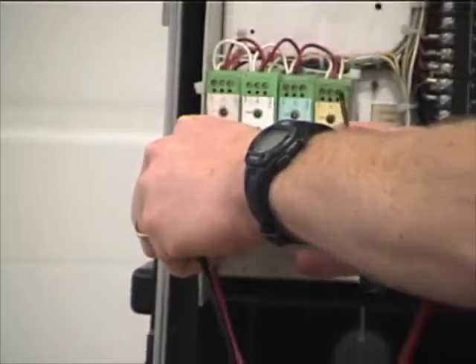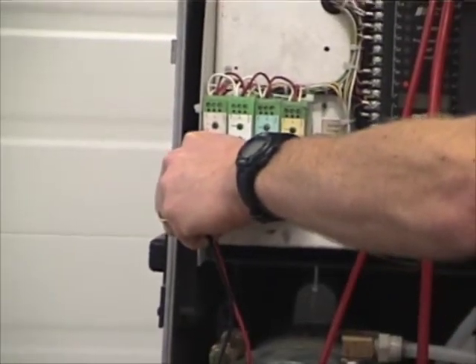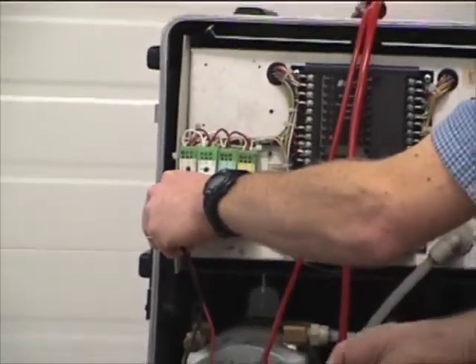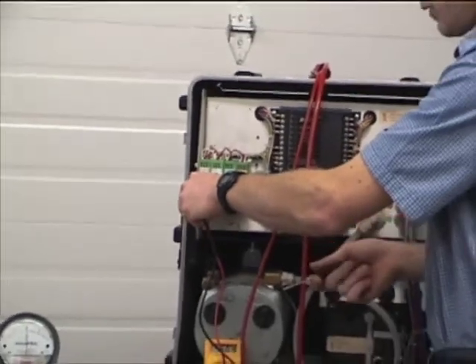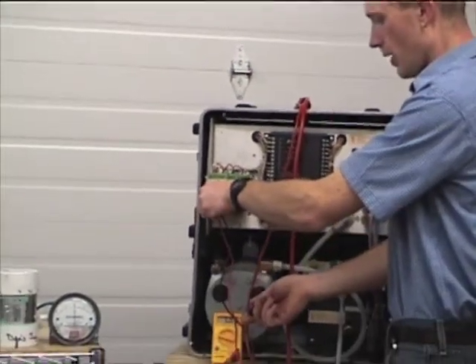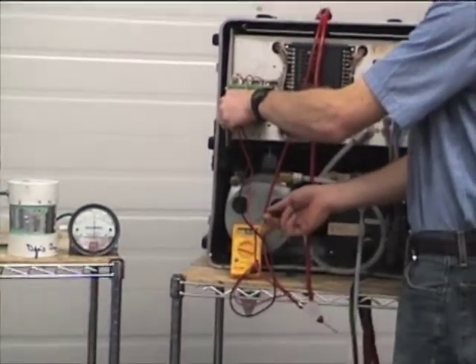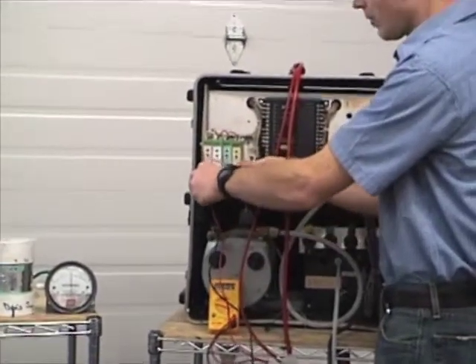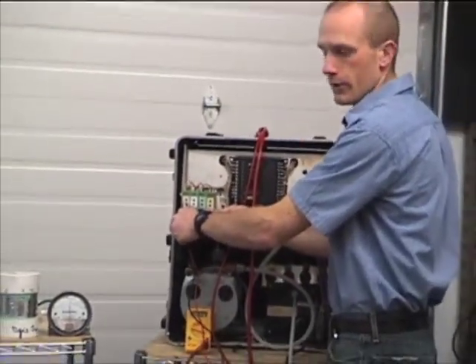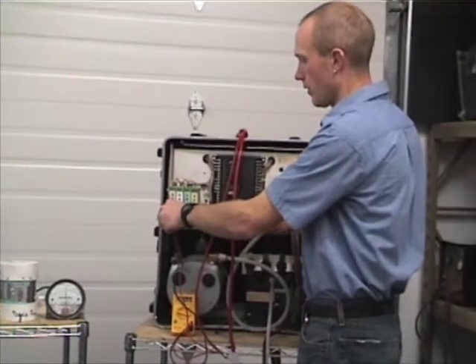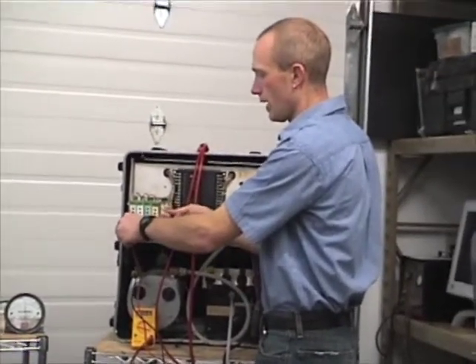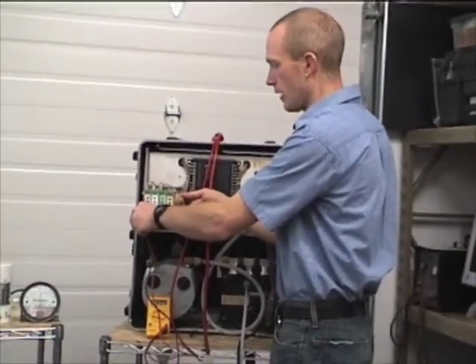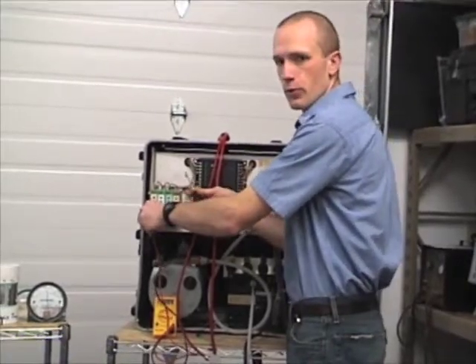With those in those positions, and then the machine started, it'll get a little loud when I start it, so I'll just tell you now. We're going to set the voltmeter to 13 millivolts, and you do that by adjusting the bottom potentiometer on that amplifier board. Again, this is one per line, so we're going to have to do this for each line. For this demonstration, we'll just do one line.